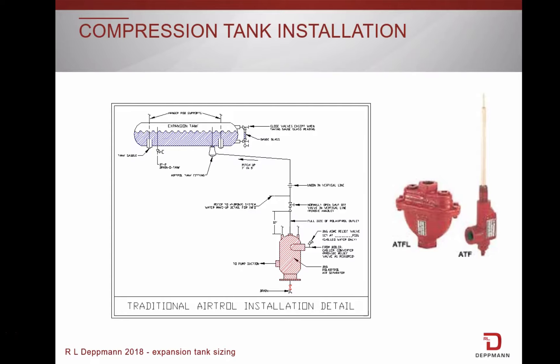Here you will see a typical installation detail for a compression tank. Any piping connected between the air separator and the compression tank must be pitched up to the tank. A compression tank starts with atmospheric pressure and is not normally pre-charged. The Airtrol fitting helps establish proper initial liquid level in the compression tank when filling the hydronic system. They also help maintain proper system pressurization by directing released air to the compression tank during system operation, and permit cooler liquid flow to the boiler during the off-cycle as system liquid cools.